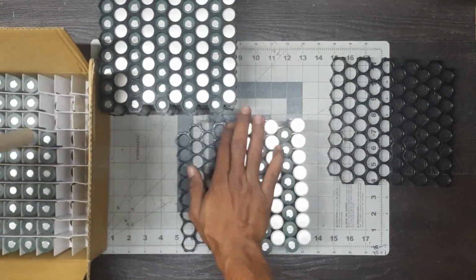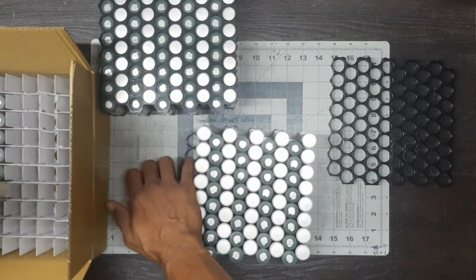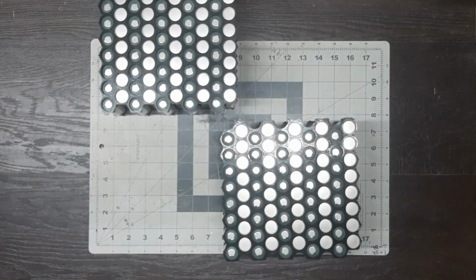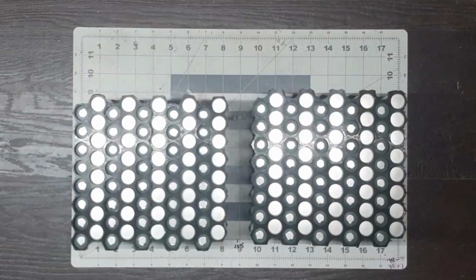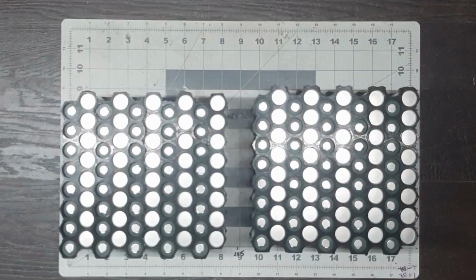In this configuration, each row of cells from top to bottom is a parallel group of 8 cells that will connect in series. When we connect cells in parallel, all the positives and all the negatives in that group are connected together. This means that they will charge and drain together, and their capacities and continuous current, or C rating, their amp rating, will be multiplied by the number of cells in that group, in this case 8. The nominal voltage will remain the same as a single cell here at 3.6 volts.